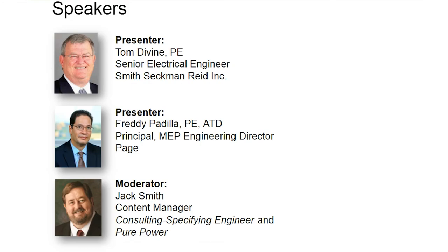Well, for emergency systems, the requirement reads pretty specifically that the capacity will be suitable to serve all loads simultaneously. All loads to be operated simultaneously is the actual wording. There may be a little bit of room for interpretation in that, but I have seen it interpreted to mean that it's the NEC calculated connected load with no diversity factors applied.